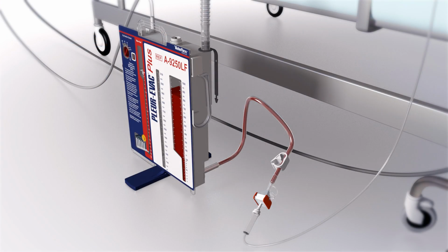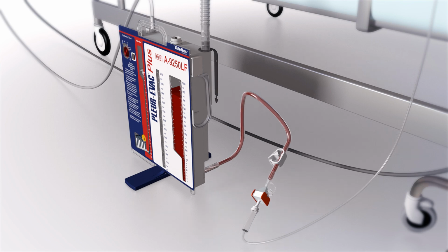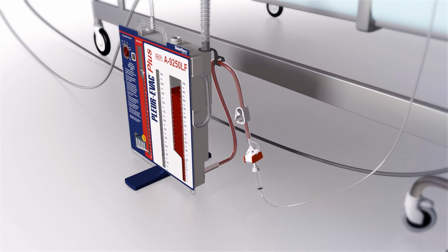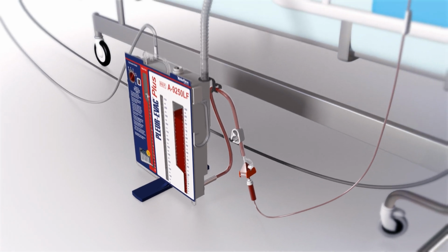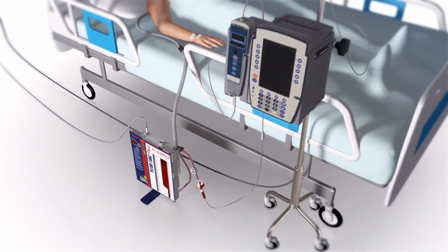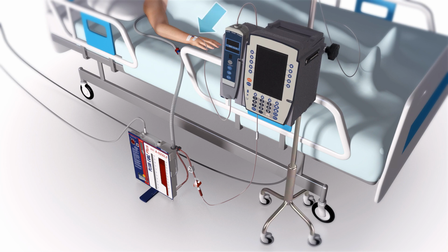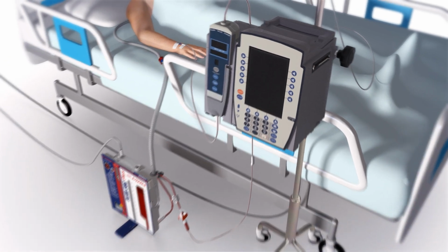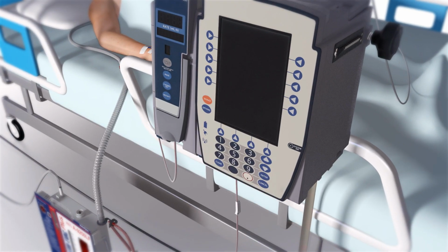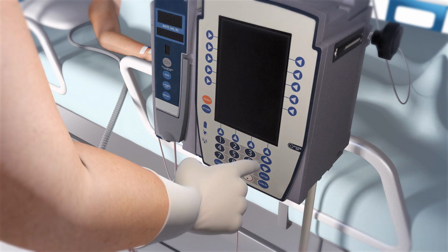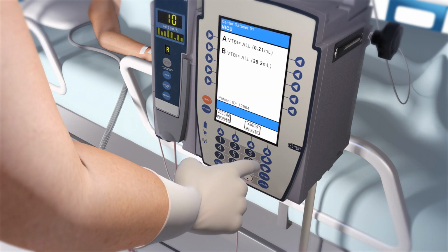Using the provided strap, position the reinfusion line, ensuring the microaggregate filter is in a spike-up orientation. Reconfirm the infusion line is filled with blood and free of air prior to beginning reinfusion. Connect the infusion line to the patient's catheter. Finally, after attaching the infusion line to the patient's catheter, set the infusion rate as prescribed.